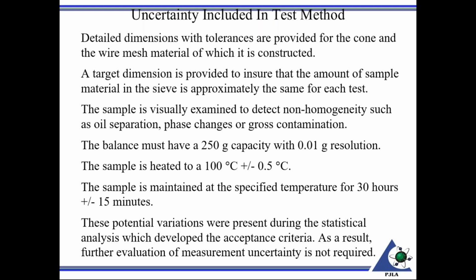There are many of them out there. I also want to mention there is an ASTM standard, ASTM E2554. Often with testing, results are based on repeatability or reproducibility. You could have a controlled sample in your lab that you utilize to capture this data. This ASTM standard describes techniques for laboratories to estimate the uncertainty of a test result using data from testing results on a controlled sample.